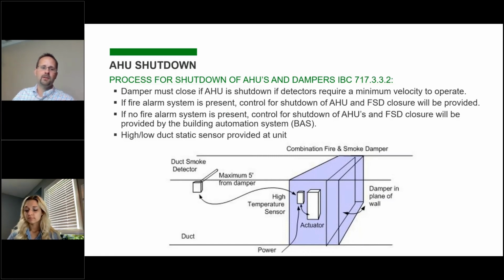Another important thing with your AHU is to have a high or low duct static sensor at your unit, because if smoke dampers that close off the majority of that airflow close, you could blow out a piece of ductwork. With most DDC systems, those are a pretty reliable, pretty fast way of preventing damage to your unit or your ductwork. It's not like a blast door that will be open and no one will know, leaking air into the plenum for years to come.